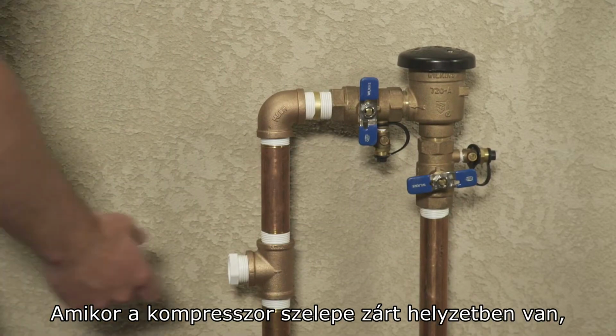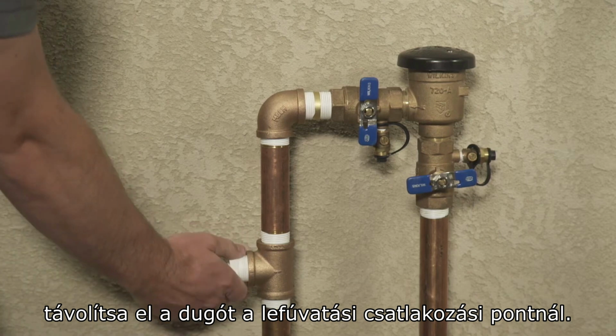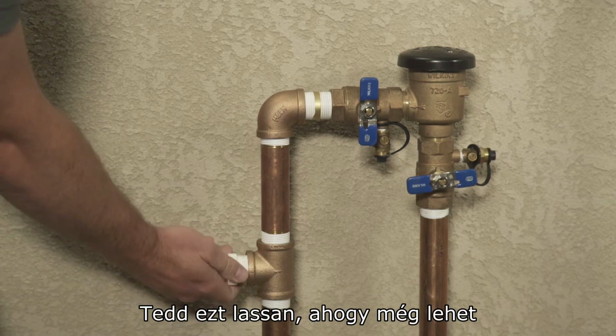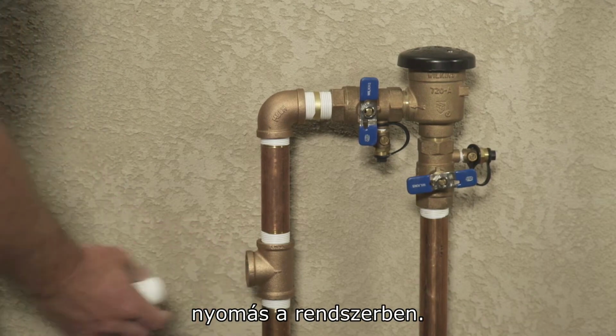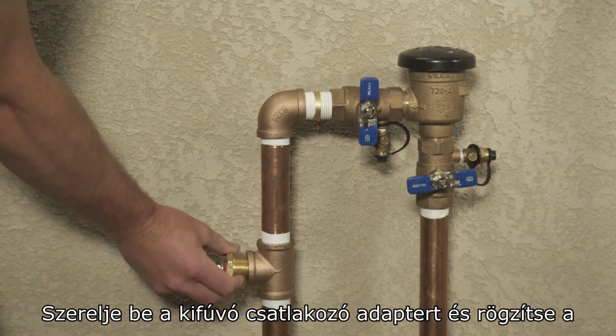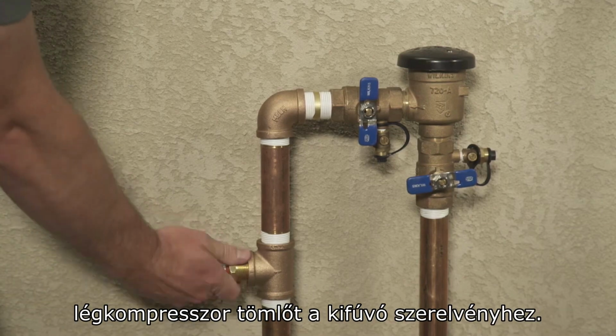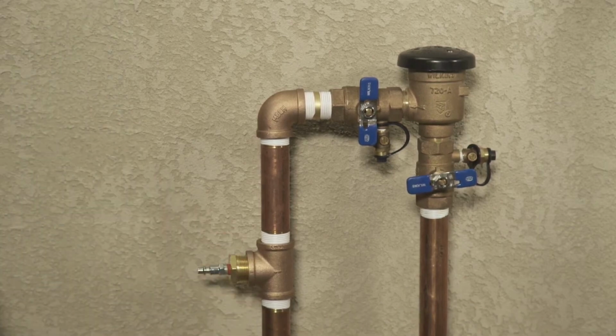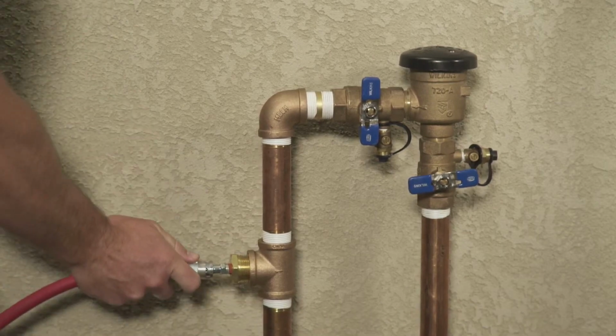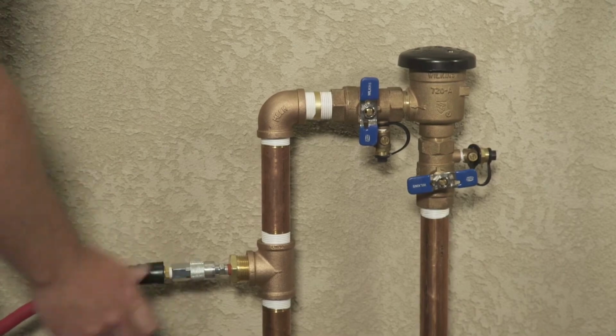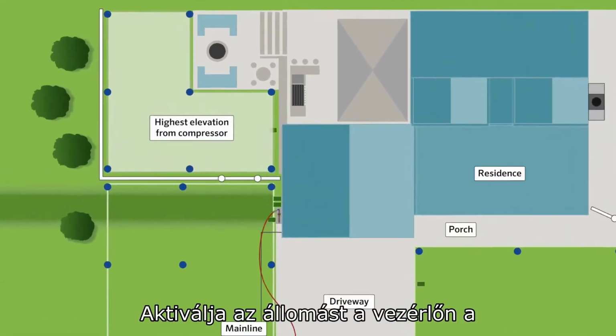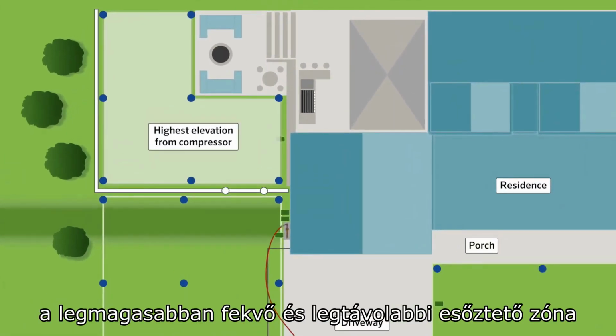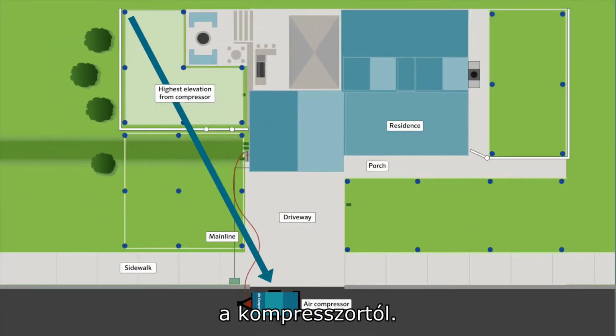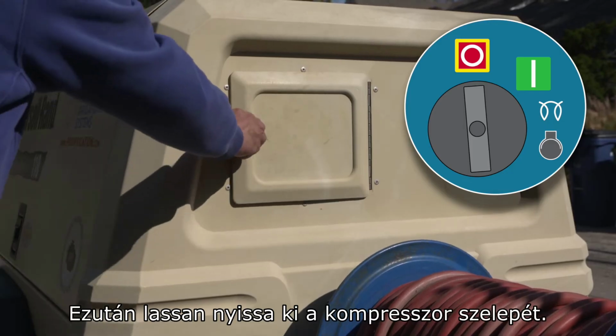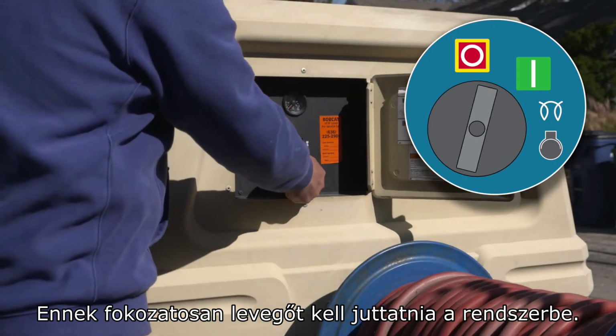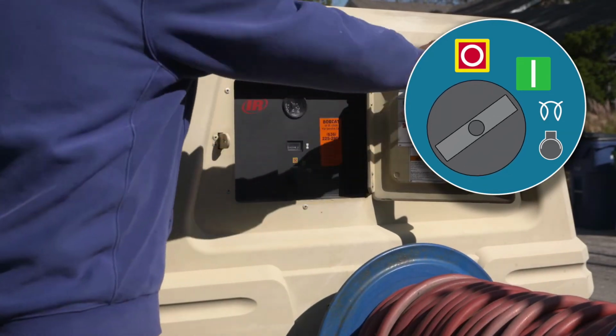With the compressor valve in the closed position, remove the plug at the blowout connection point. Do this slowly as there still may be pressure in the system. Install the blowout connection adapter and attach the air compressor hose to the blowout fitting. Activate the station on the controller for the zone of sprinklers highest in elevation and furthest from the compressor. Then slowly open the valve on the compressor. This should gradually introduce air into the system.